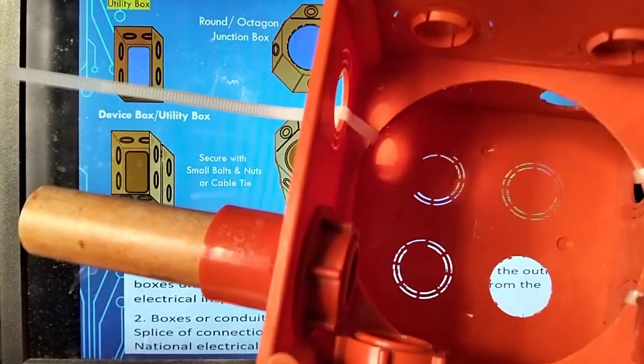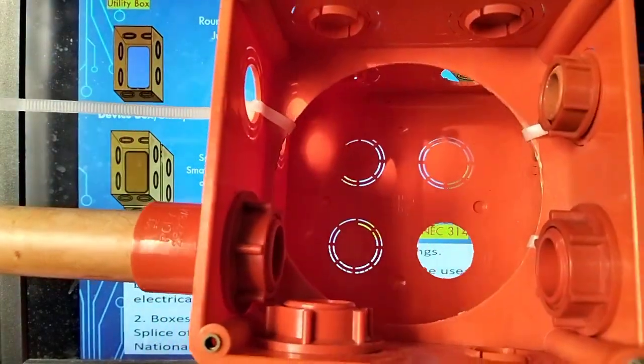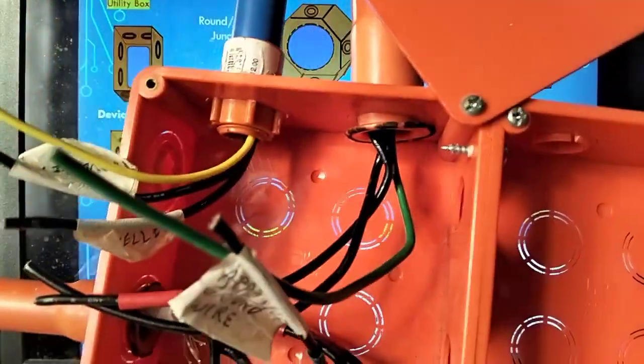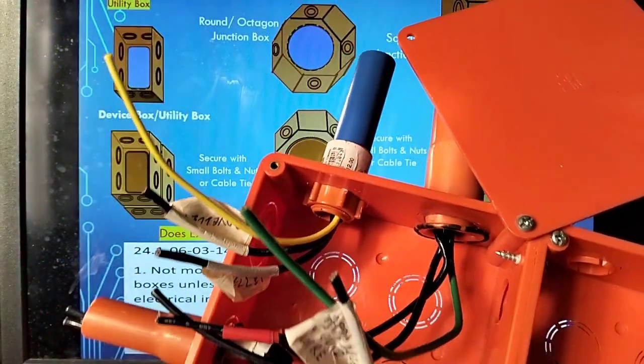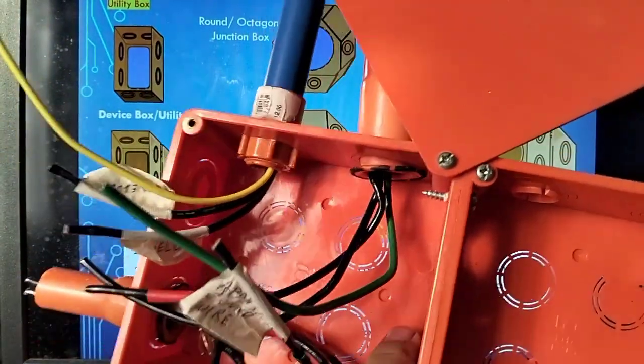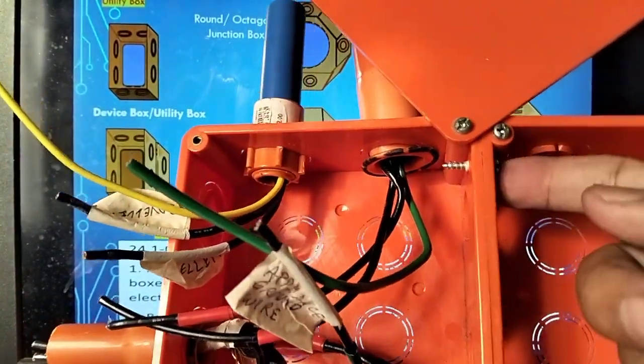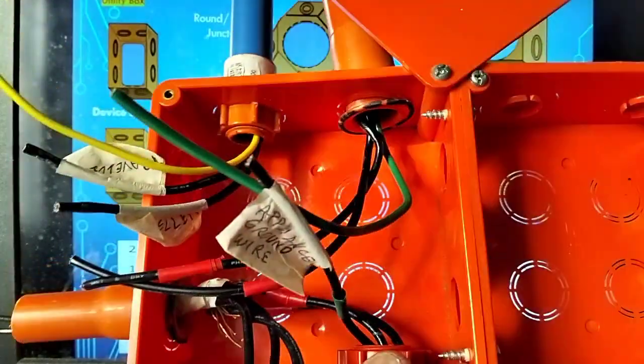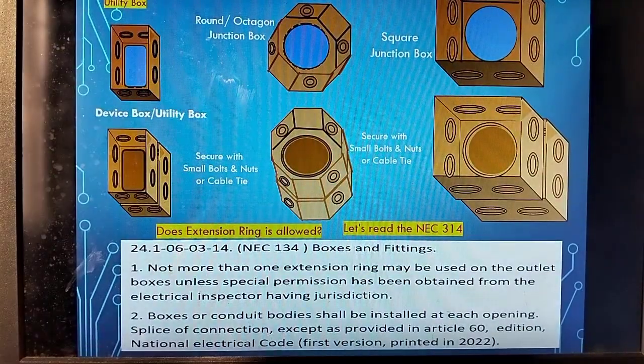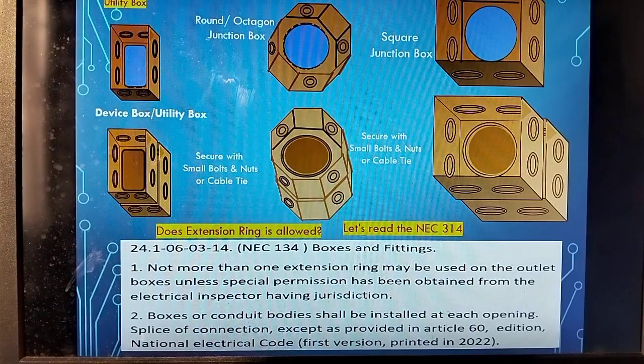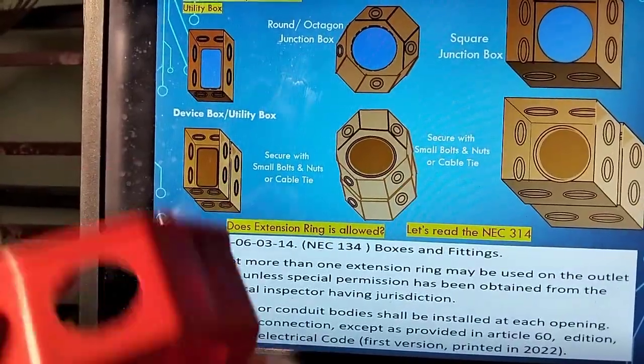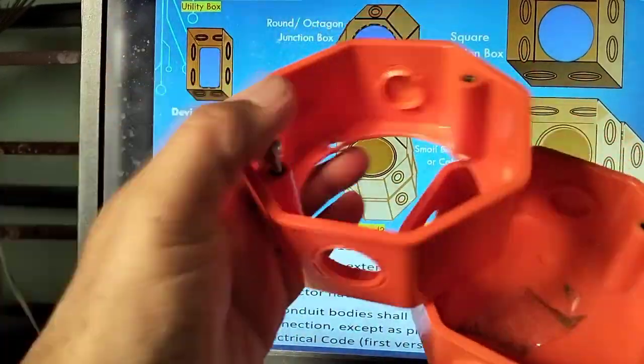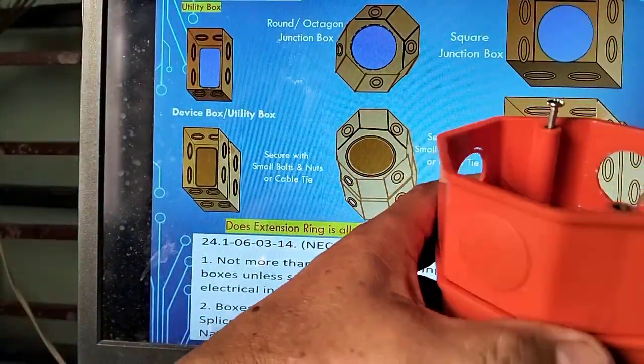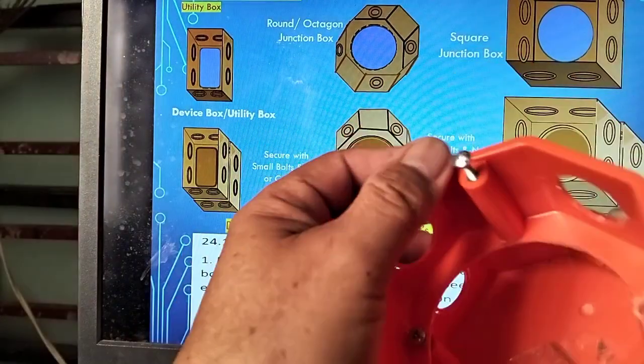But there's an advantage if you have a hole saw, much better like this. It was only in one focal point. Whereas if you use this one, even if you don't have a hole saw, you can still extend the square box, but you have to use screw or cable tie. You can use, no? And this one also, no? Over the top for the junction box, you use the hole saw and then put the screw.